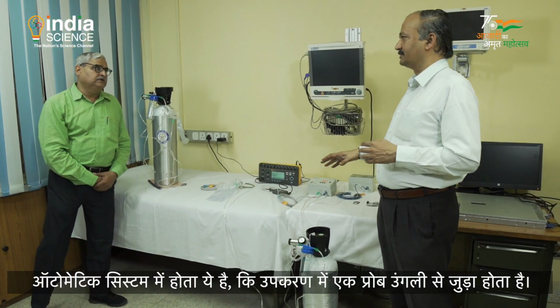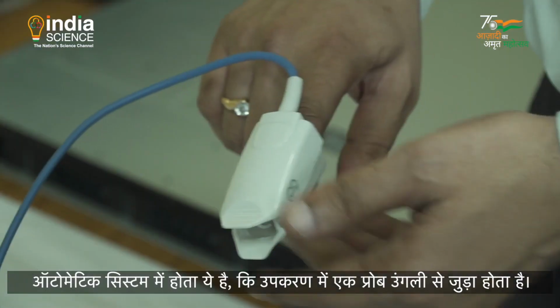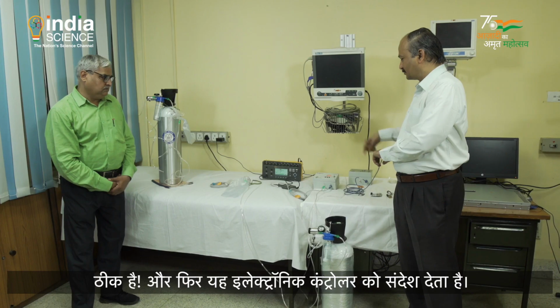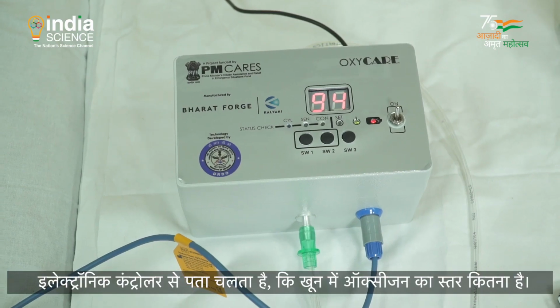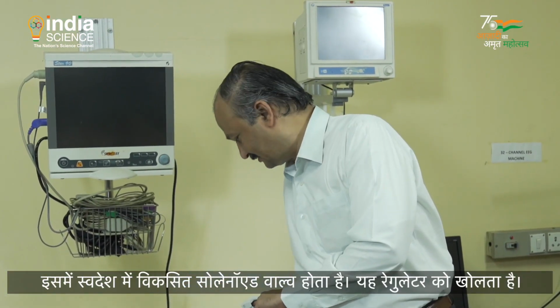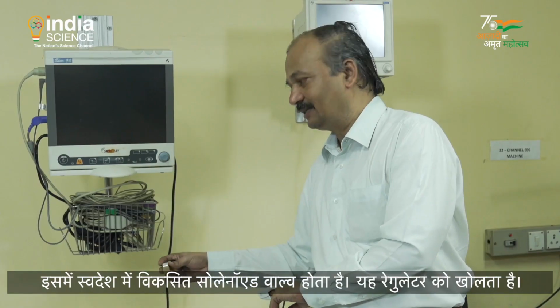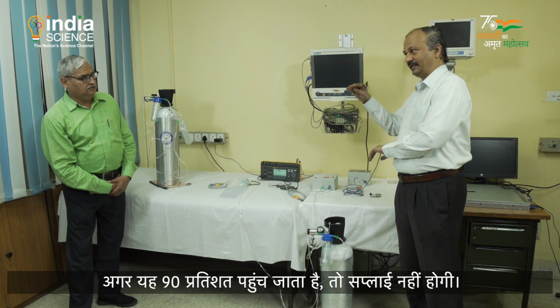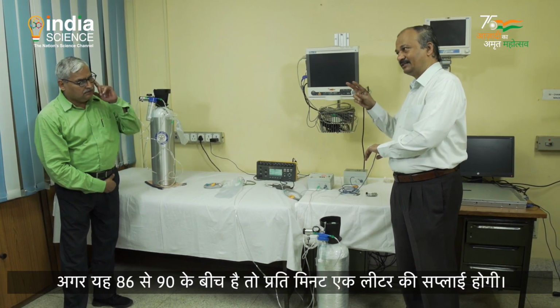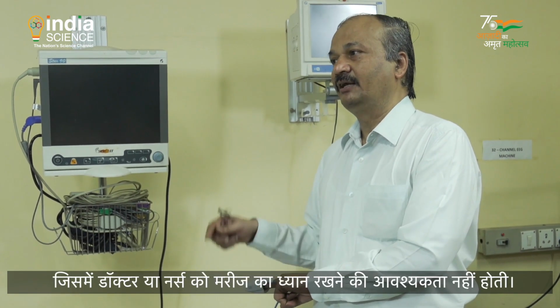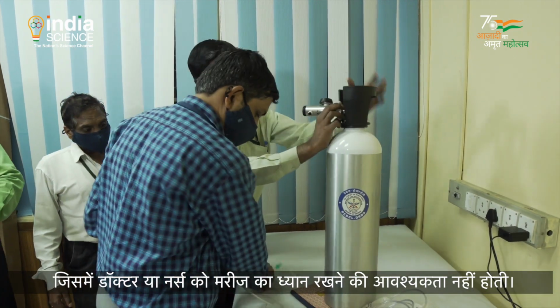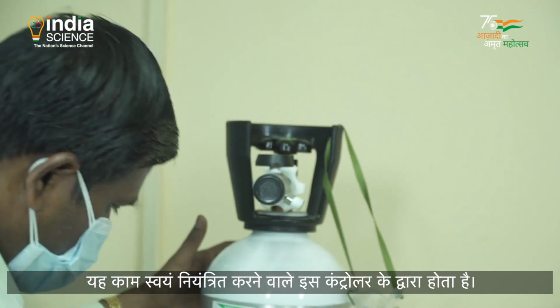In the automated system, there is an SpO2 probe which is connected to the finger, and this gives the inputs to the electronic controller. The electronic controller will process the oxygenation level in the blood, and there is an indigenously developed solenoid valve inside this, and it will open up the regulator and start regulating the supply of oxygen. If it is up to 90%, there won't be any supply. If it is between 86 and 90, it will start supplying 1 liter per minute. When it comes down to 70 and below, it starts giving out 5 to 10 liters per minute. It can go up to 15 liters per minute. So that is the beauty of the system, wherein the doctors or the nurse need not look at the patient. This is done automatically by this particular autocontroller.